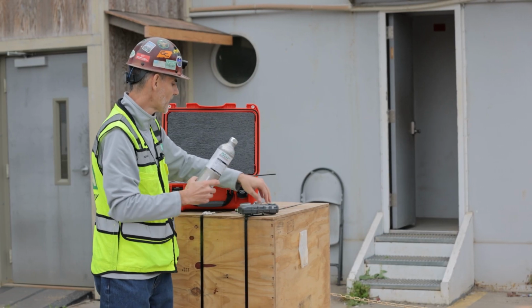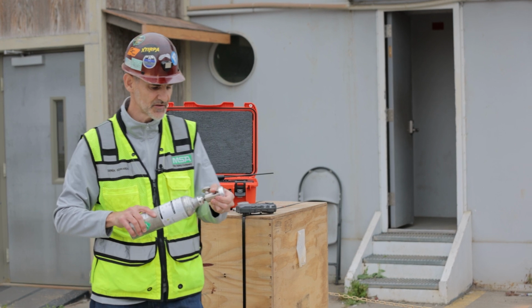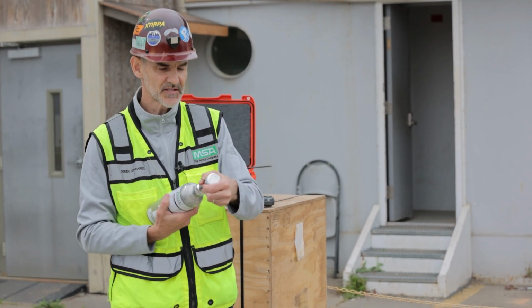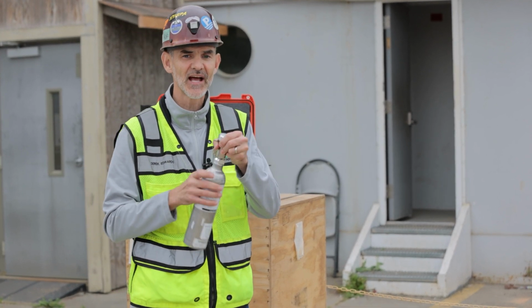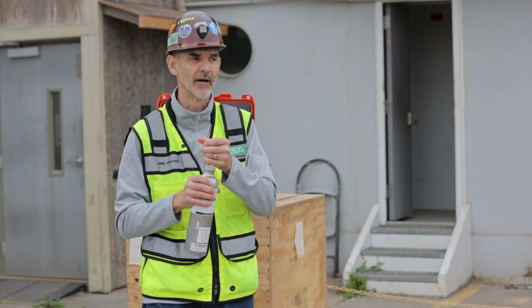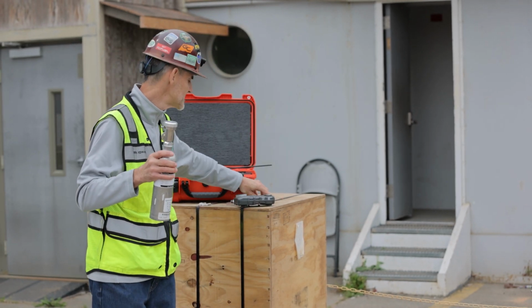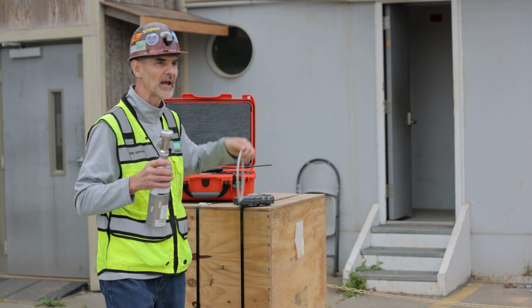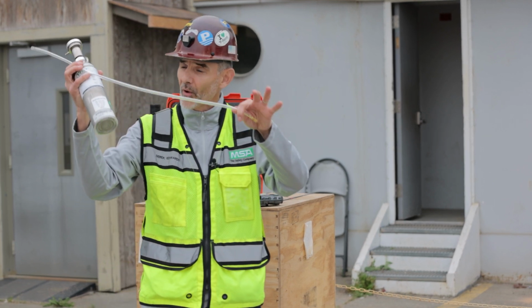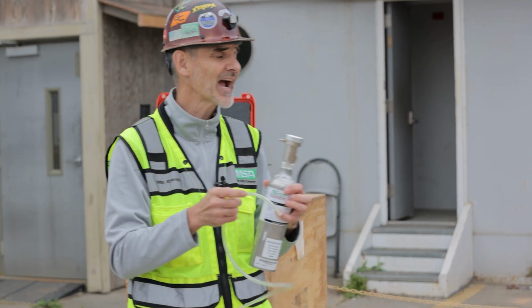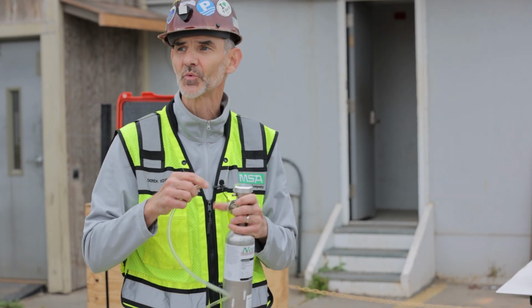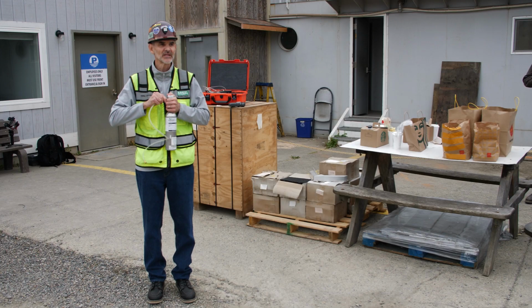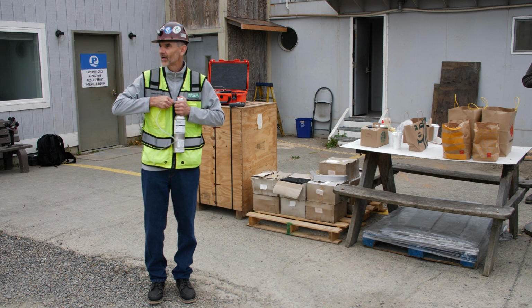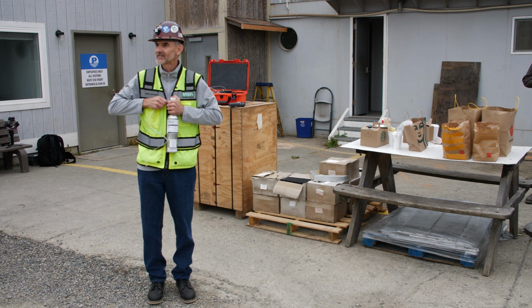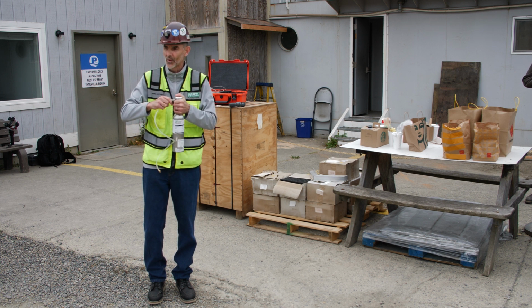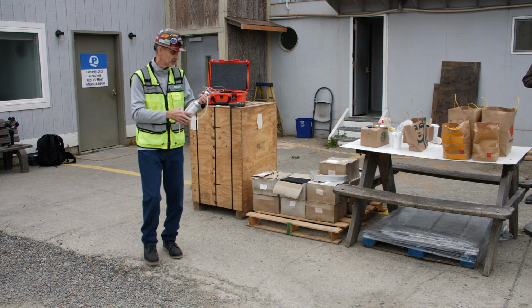Next, we will go over a bump test for the instrument. It is important that these instruments are tested before you use them. And without going into too much detail, I will just tell you that a bump test with calibration gas is just a check to see if the instrument is reading correctly. If the instrument's not reading correctly, it may go into false alarm. It's not going to be an accurate reading. We want to make sure that we're accurate.